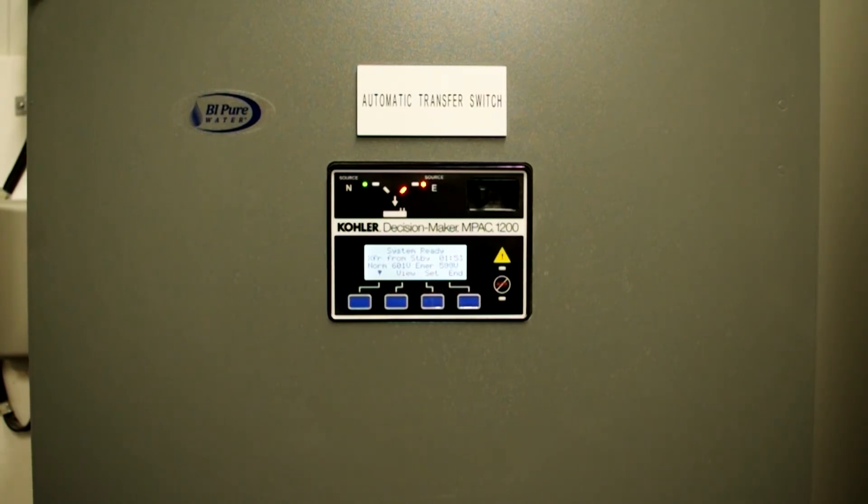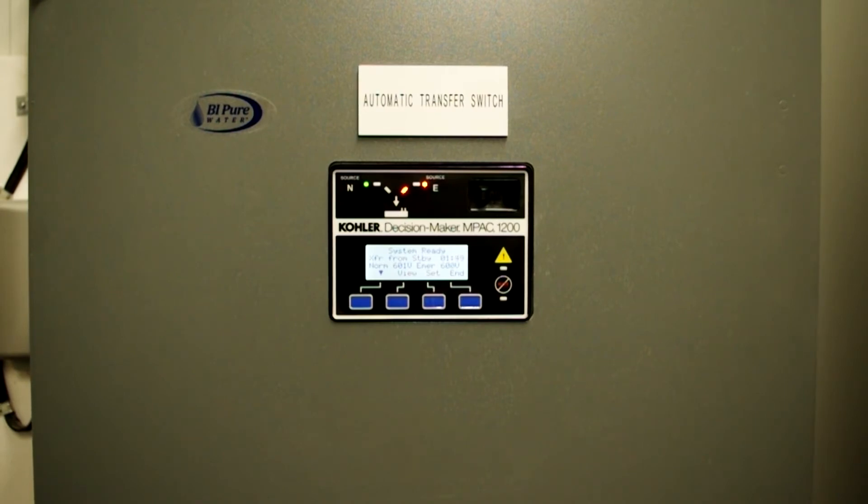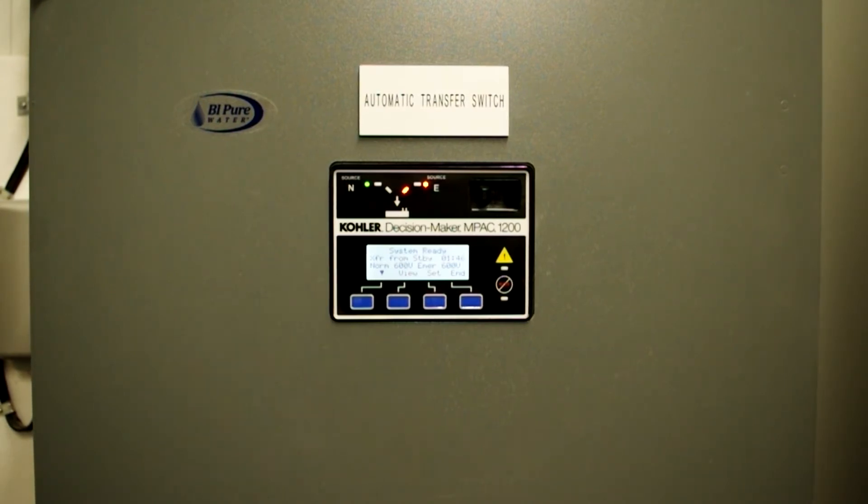You'll see a countdown timer on the generator, countdown for two minutes. This is so that it doesn't short cycle in case the power goes out again, the generator can keep running.